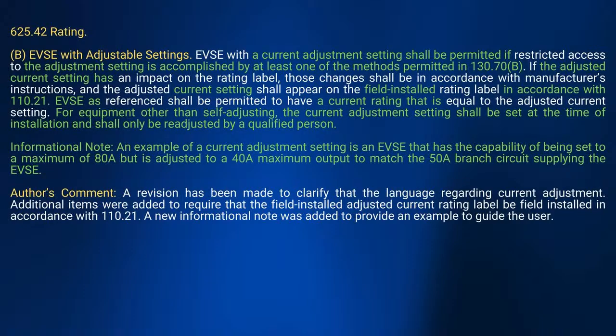Now what they did here, we start in 625, and this is where we get into EVSE. Basically what they did was make a revision to clarify certain language regarding current adjustment. They added additional items requiring that this field-installed adjusted current rating label be field installed, and when you install it, you do so in accordance with 110.21. I've gone over that so much. But they did add an informational note, just an example to help guide the user, giving an example of a current adjustment setting for your EVSE.